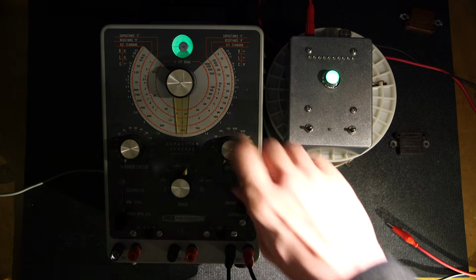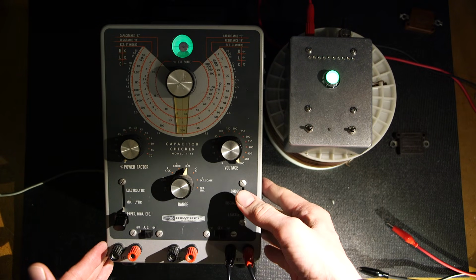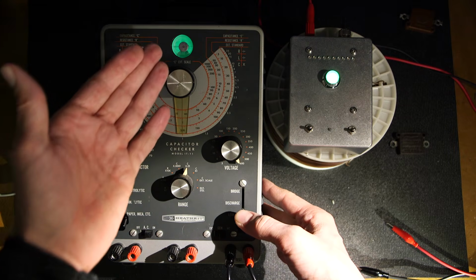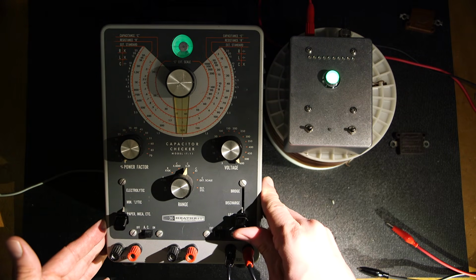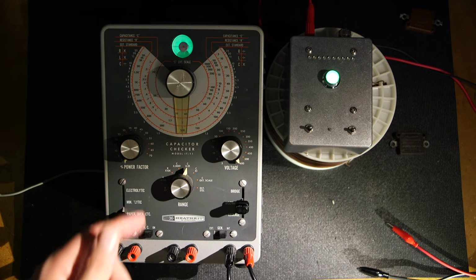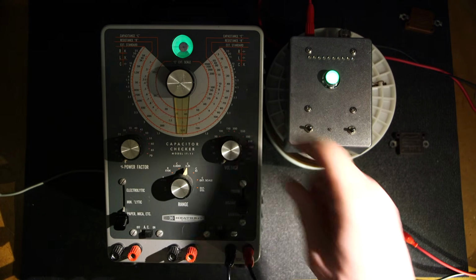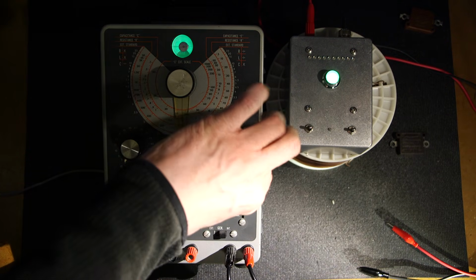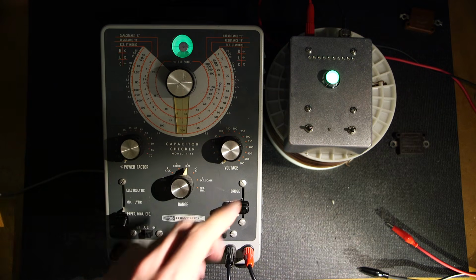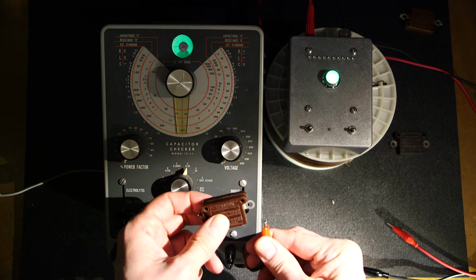Let's move that out of the way, again up to 600 volts. Leakage, no problems. Again, we're on the paper and mica setting, 600 volts here, turn that rate down. Even though it's on discharge, I always like to turn this down first before I handle anything, just as an extra precaution.